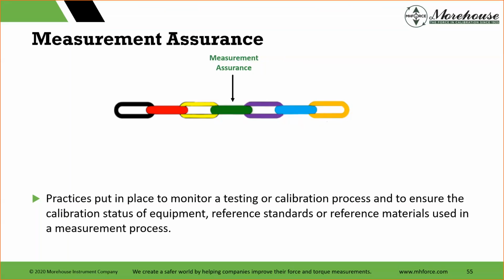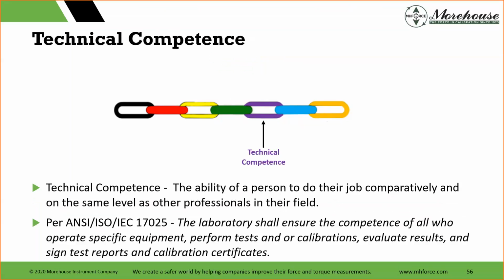I can see if maybe a new technician, I can use that to train the new technician. Do they have it? Do they have the technical competence? And speaking of technical competence, the ability of a person to do their job comparably and on the same level as other professionals in the field. Have they been trained? Nothing's really better than, at the end of the day, you train somebody for all this stuff, and then you give them that gold reference, that all your other techs, the numbers are really good, nicely grouped together, and now this technician is going to go with a gold reference, one that's just known phenomenally well. And here the laboratory shall ensure competence of all those who operate specific equipment, perform tests and or calibrations, evaluate results, and sign test reports and calibration certificates.